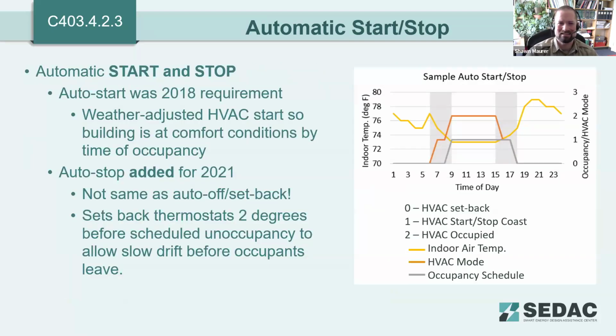The 2018 IECC had automatic start language in it. The 2021 has now added automatic stop as well. Automatic stop just allows the building to start coasting slightly before the scheduled unoccupied time, so that spaces will drift only about 2 degrees before the scheduled unoccupancy period begins. This is just a way to conserve energy, particularly as peak energy draws tend to happen around the same time that buildings are starting to go unoccupied, around 5, 6 o'clock in the evening. So it's a demand control measure built into the code now.